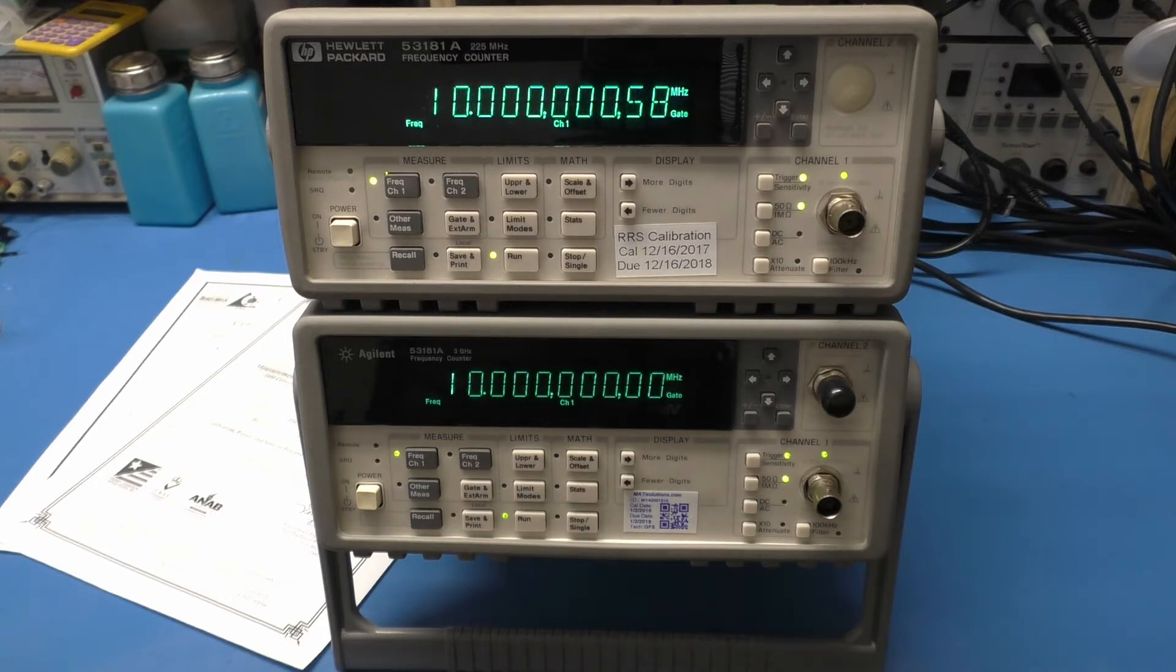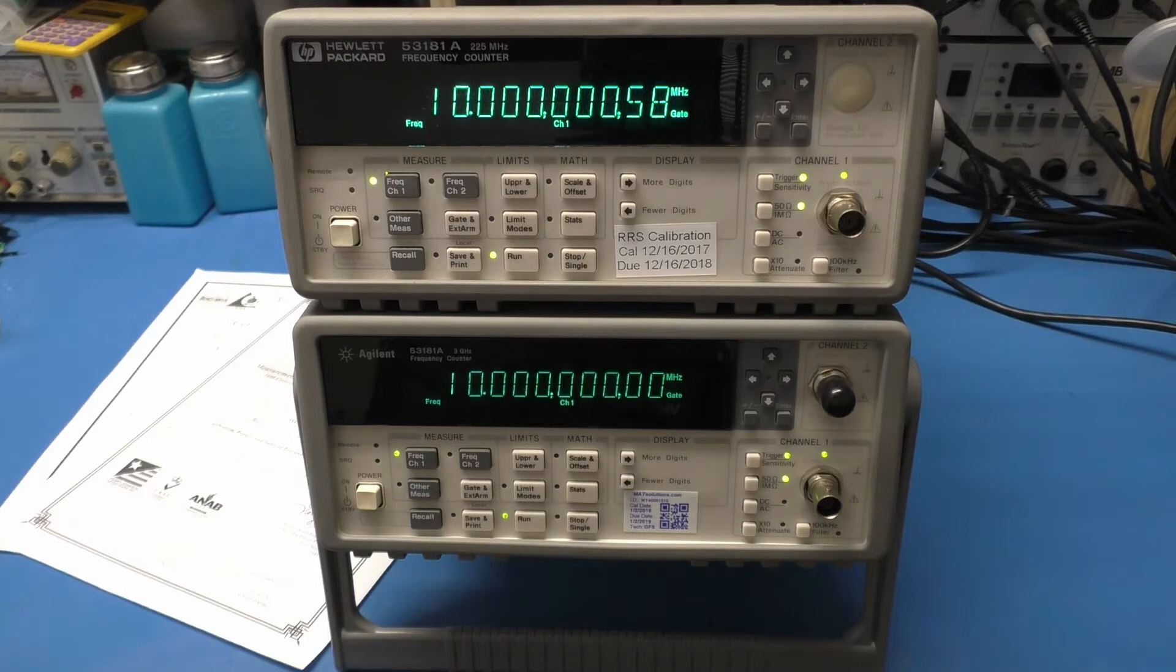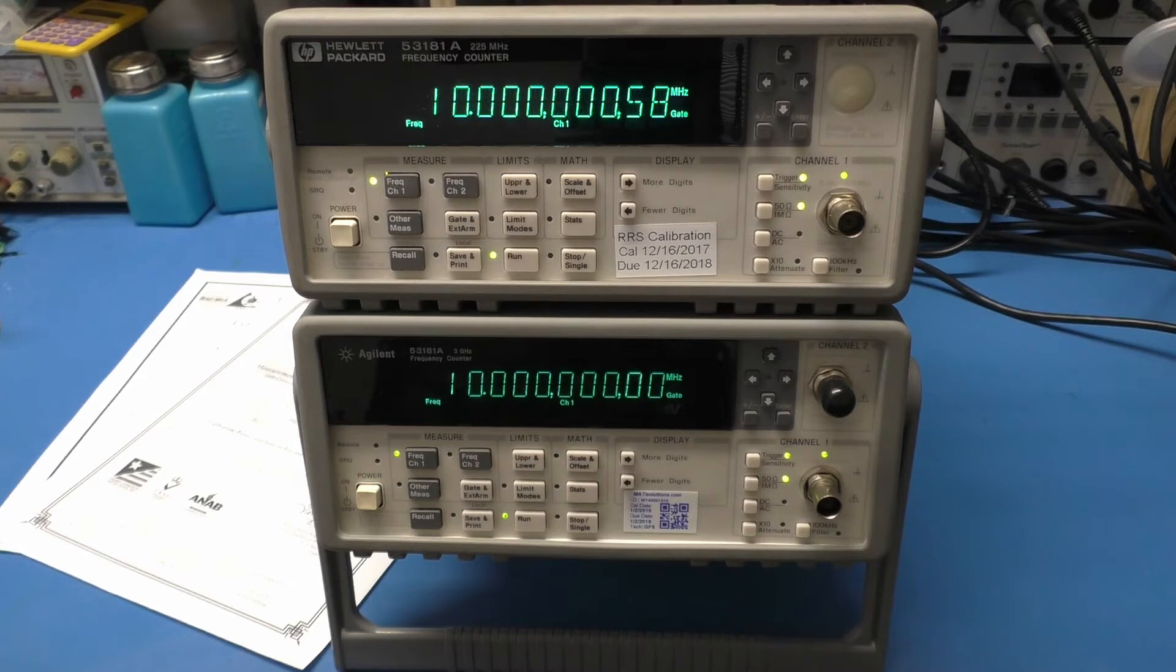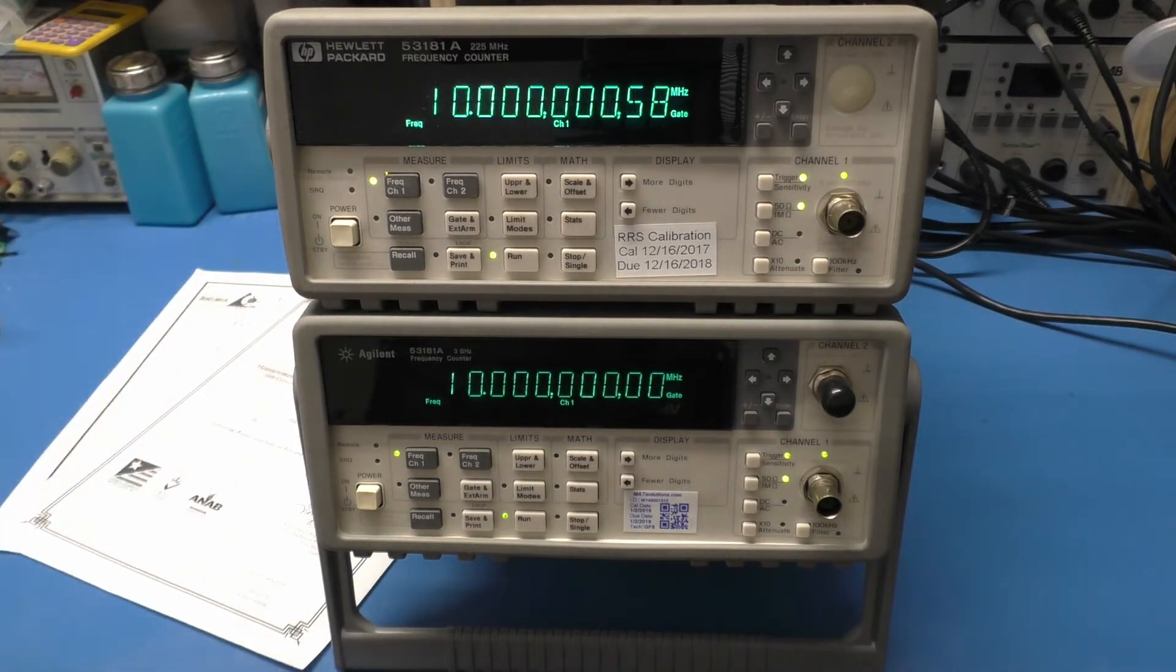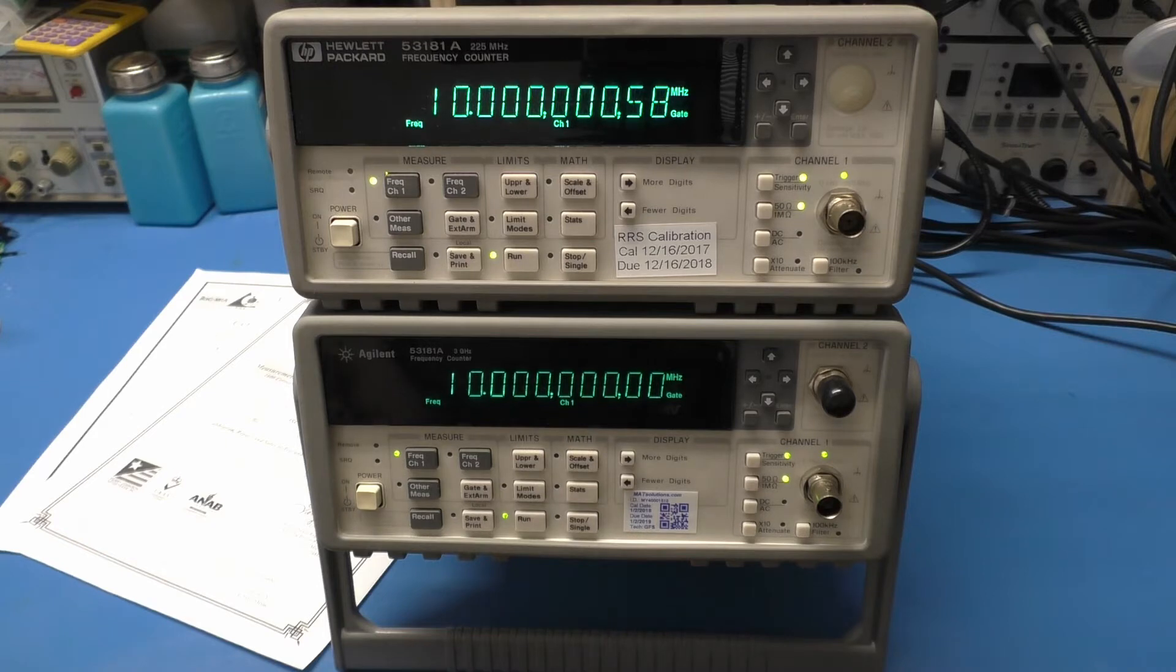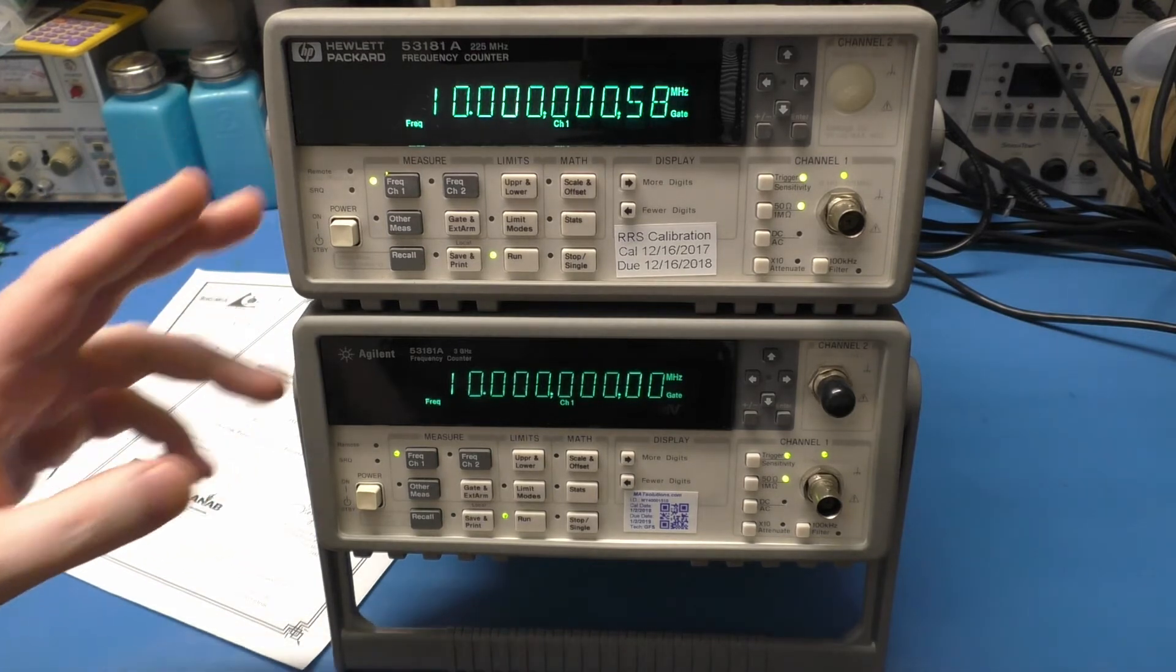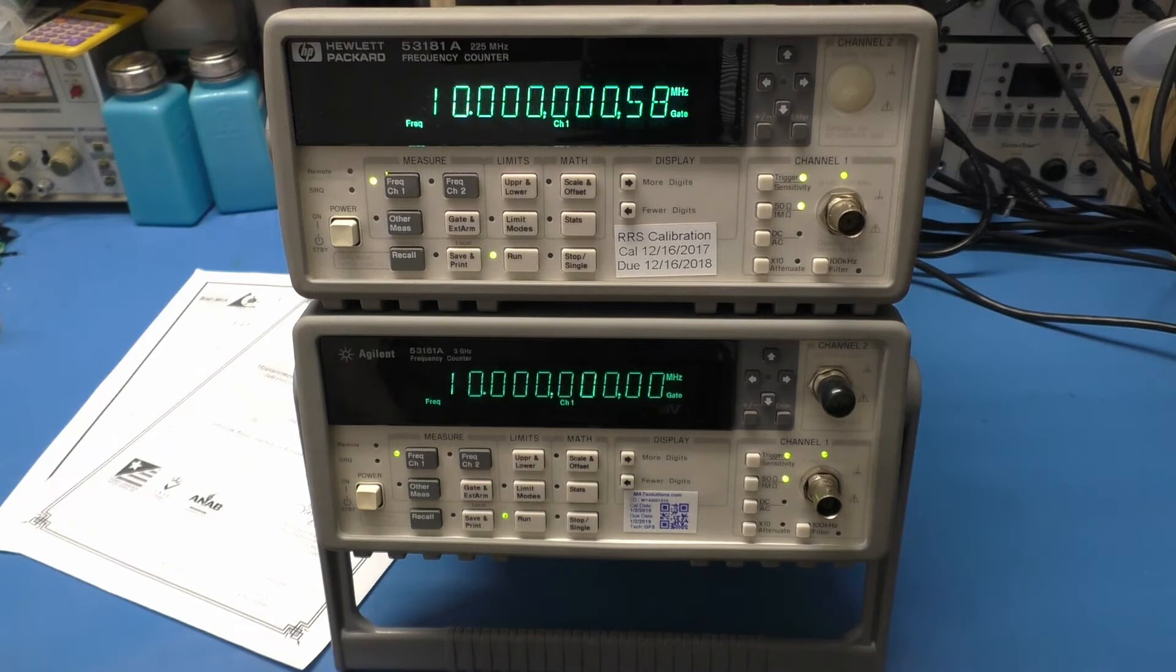They both said that the calibrations would be provided upon purchase. In other words, they would do the calibrations when you got it, which makes sense. That's how most everybody operates. They're not going to do it until you buy it because the thing could be listed for three weeks and nobody buys it. You take time to stabilize and a lot of times they'll usually let them run and let them cook for 24 plus hours to make sure that the ovens have stabilized because they take a while. They're usually up to temperature in 15 minutes but they take a good long time to actually stabilize.